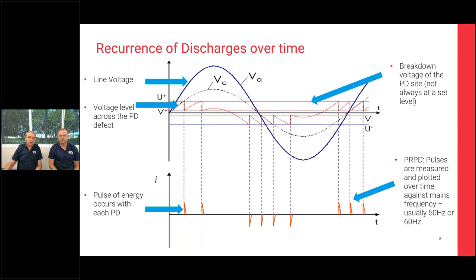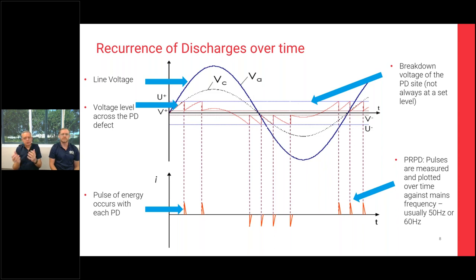When you see PD pulses from cavity-type discharge, they occur on the rising and falling edge of the sine wave — a certain number but not too many per cycle — consistent in position but slightly random in amplitude. Surface discharge tends to occur at the peaks of the voltage and be more frequent.